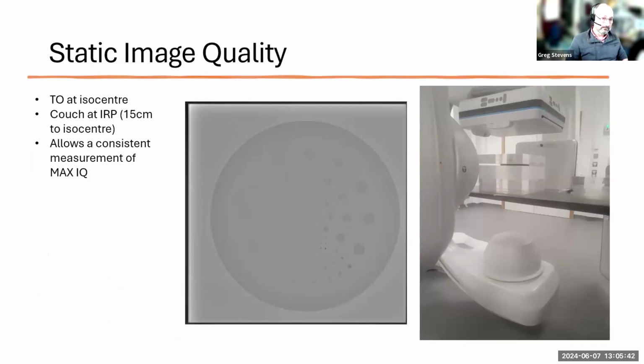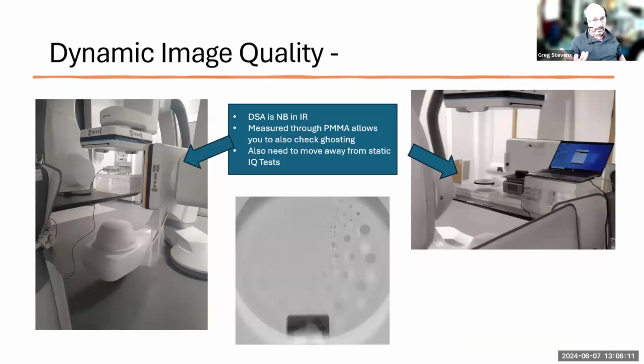What I've actually done there is set the system up so that I've got 15 centimeters of Perspex on the couch at the interventional reference point, which means the test object is at the isocenter, and that makes it much easier to rotate the A and B planes simultaneously and then do the measurement for the other plane. It just makes your life a little easier. That gives you a maximum image quality, but beware that it is not the clinical image quality your clinicians will be seeing.